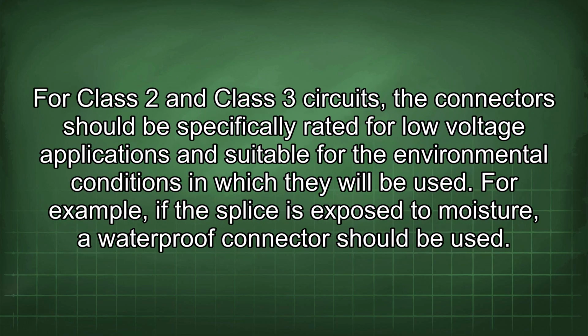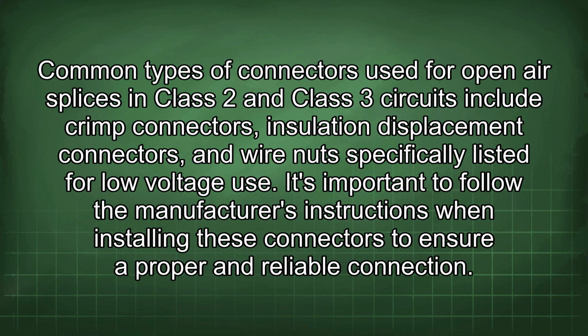For Class 2 and Class 3 circuits, the connectors should be specifically rated for low voltage applications and suitable for the environmental conditions in which they will be used. For example, if the splice is exposed to moisture, a waterproof connector should be used. Common types of connectors used for open-air splices in Class 2 and Class 3 circuits include crimp connectors, insulation displacement connectors, and wire nuts specifically listed for low voltage use. It's important to follow the manufacturer's instructions when installing these connectors to ensure a proper and reliable connection.